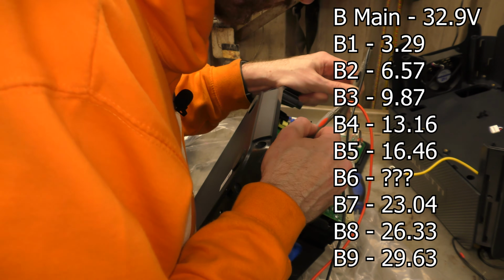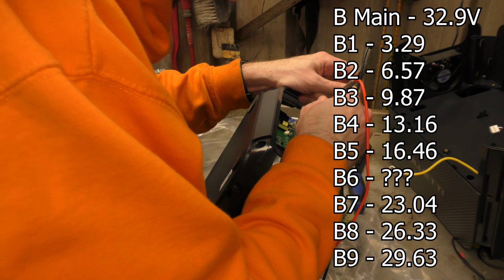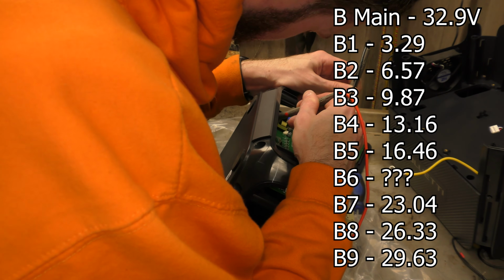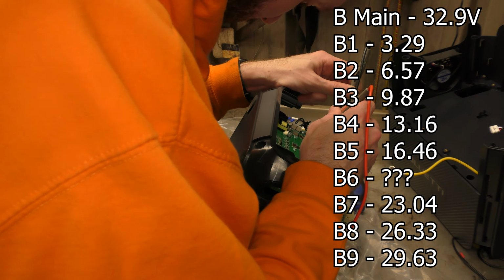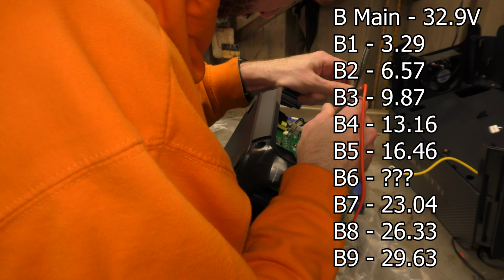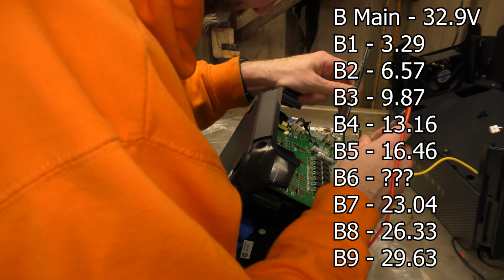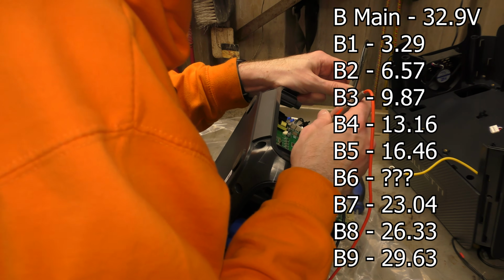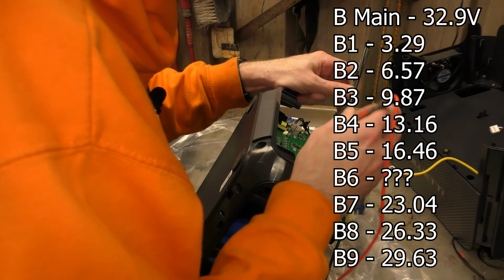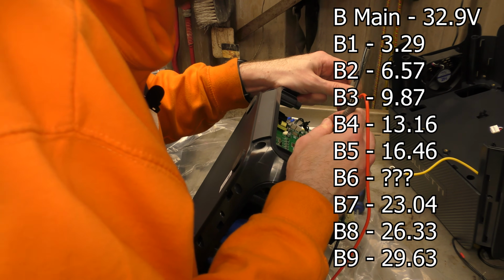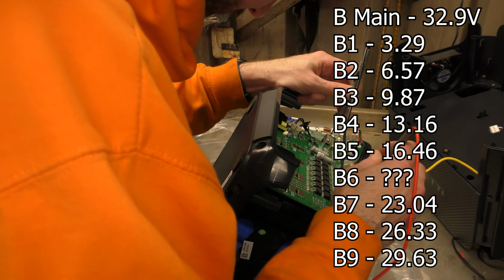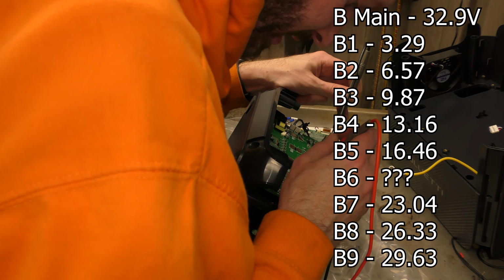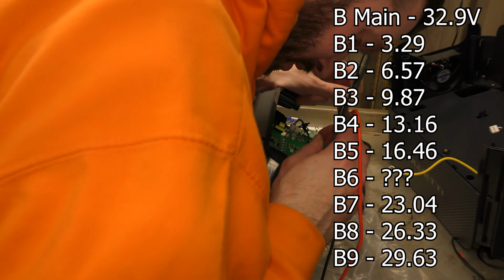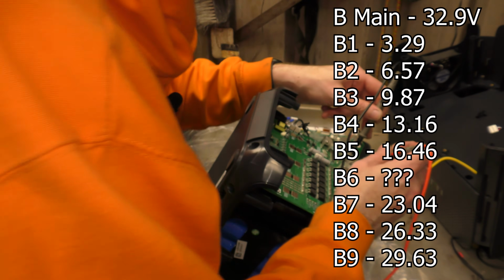32.9 volts, 33 volts. So between battery negative and battery 1, I've got 3.292. Battery 2, 6.57. B3, 9.87. P3, B4, 13.16. B5, 16.46. B7, 23.04. B7, B8, 26.33. And B9, 29.63. Then the full battery voltage was 32.93, and then nothing up here because the BMS has turned the output off.